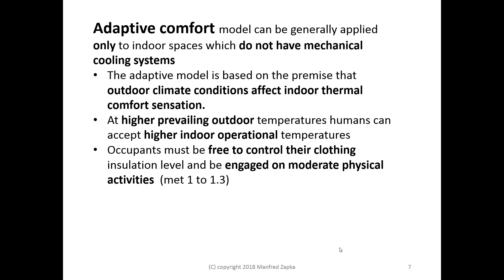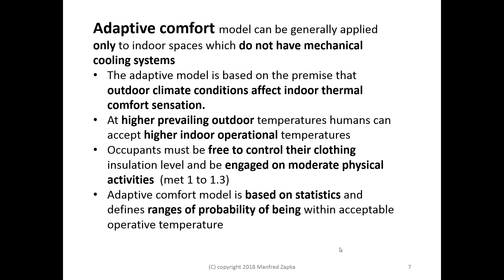The occupant must be free to control their clothing and must be engaged in moderate physical activities, MET 1 to 1.3, which is typically office conditions. They should be free to control their clothing insulation — meaning they are not forced to wear thick jackets. The adaptive comfort model is based on statistics and defines ranges of probability within acceptable operative temperatures.